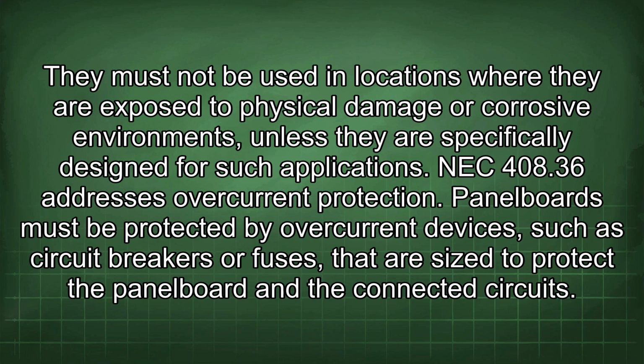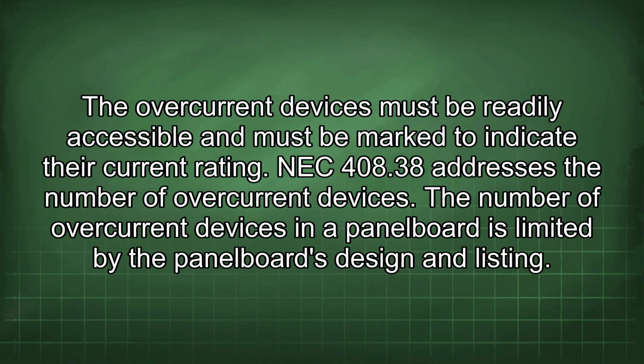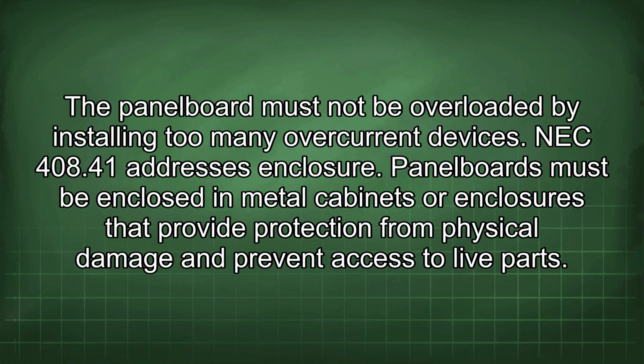NEC 408.36 addresses overcurrent protection. Panel boards must be protected by overcurrent devices such as circuit breakers or fuses that are sized to protect the panel board and the connected circuits. The overcurrent devices must be readily accessible and must be marked to indicate their current rating. NEC 408.38 addresses the number of overcurrent devices. The number of overcurrent devices in a panel board is limited by the panel board's design and listing. The panel board must not be overloaded by installing too many overcurrent devices.